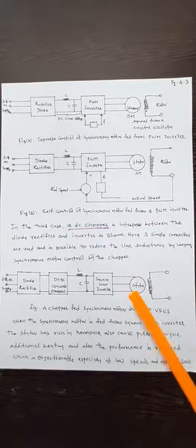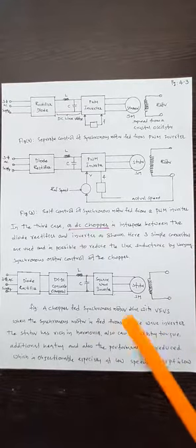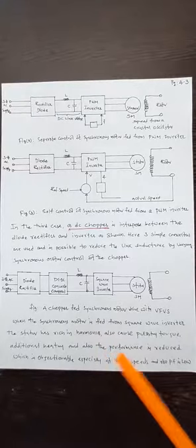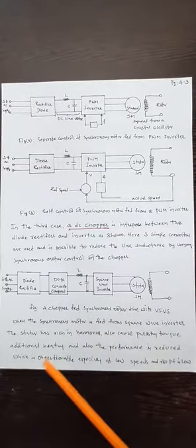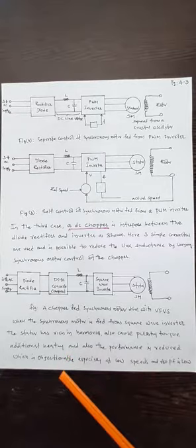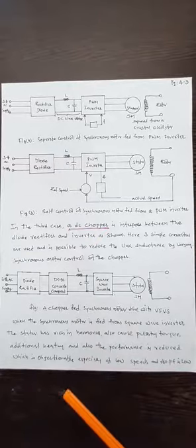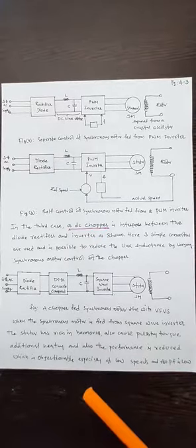When a synchronous motor is fed from a square wave inverter, the stator currents are rich in harmonics. The harmonic currents are very high, also causing pulsating torque and additional heating. Harmonics are present even in the equipment we use daily in our houses. When the system is heated, it means there are abnormal or harmonic currents in the system. So that is the indication.